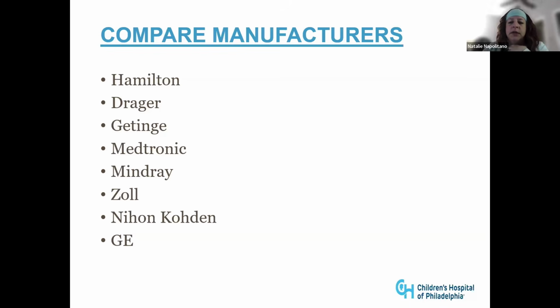And in some devices, we have a problem with Draeger in their neonatal mode. You can't do any inspiratory holds. You can't do any expiratory holds, anything. It's really just basics in their modes of ventilation, so you have to go into the pediatric modes. You need a minimum tidal volume of 20 in order to go into the pediatric mode to get some of these other functions like inspiratory and expiratory hold, which seem basic to be able to do things and collect different ventilator mechanics, but it's a problem.